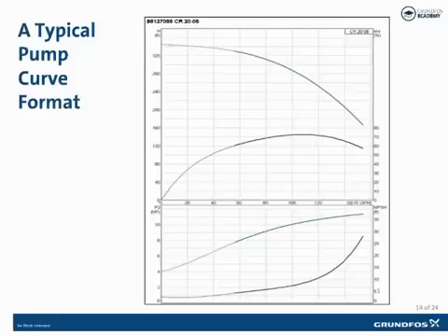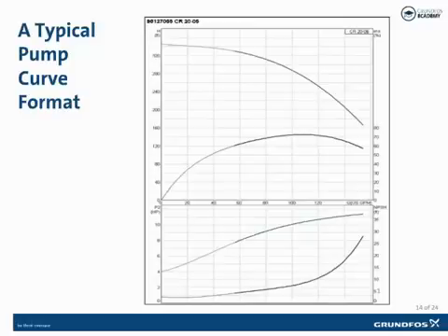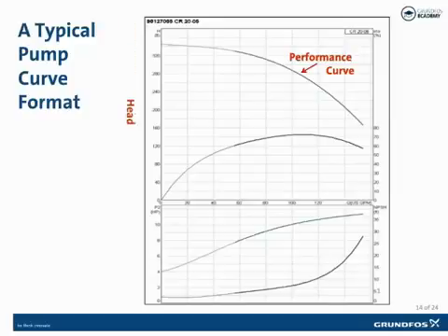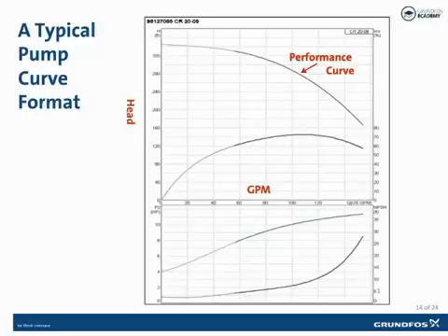A key to understanding pump operation is the understanding of pump curves. Pump curves are a map of a pump's performance and provide much of the needed information about its operating characteristics. Pump curves can be constructed in many formats, but all contain certain amounts of data. The first curve we'll discuss is the pump performance curve, also known as the head capacity curve. The vertical axis is pressure measured in feet of water or PSI, and the horizontal axis is flow measured in gallons per minute. The amount of flow a pump can produce is dependent on the head present in the system.